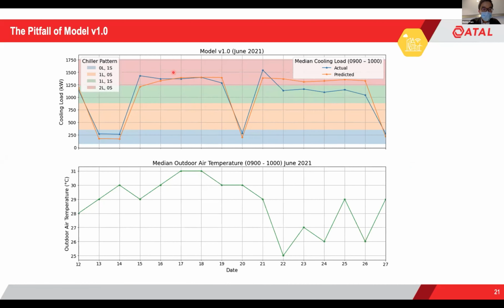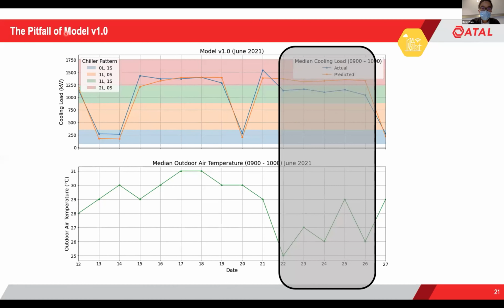You also see some colored bars here. If you'd like to operate your system in a certain cooling load range, say the orange range, like 500 to 750 kilowatts, you would switch on one large chiller. If you'd like to operate in this green range, you would switch on one large and one small chiller.